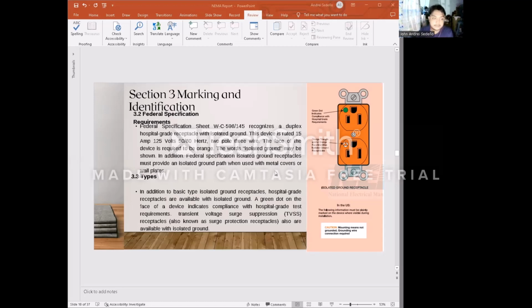Now these are the types. In addition to the basic type of isolated ground receptacles, hospital grade receptacles are available with isolated ground. A green dot on the face of the device indicates compliance with the hospital grade test requirements. Transient voltage surge suppression receptacles, also known as surge protection receptacles, are available with the isolated ground.